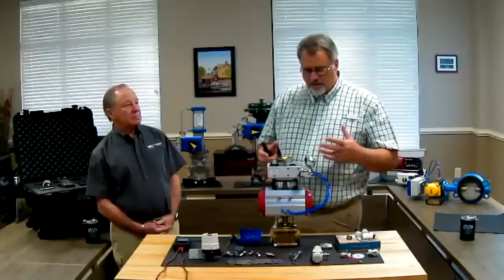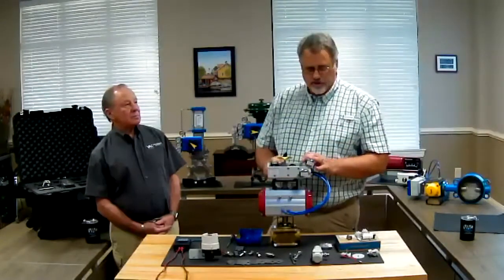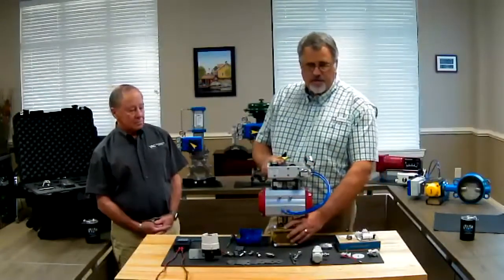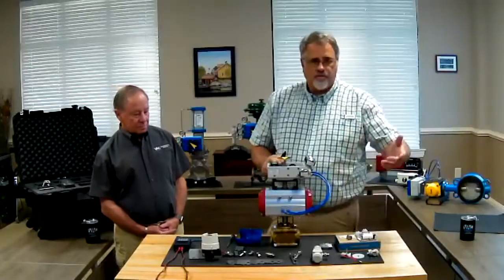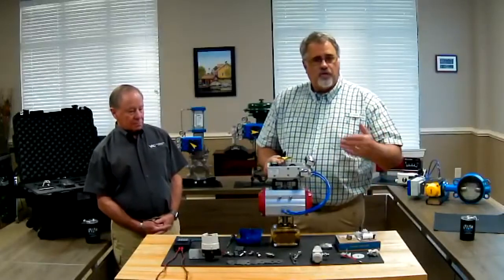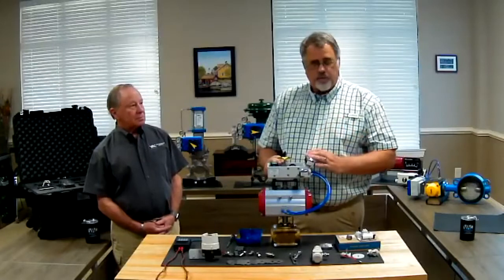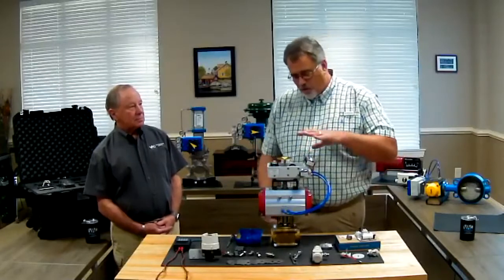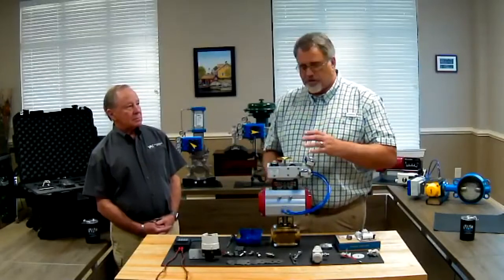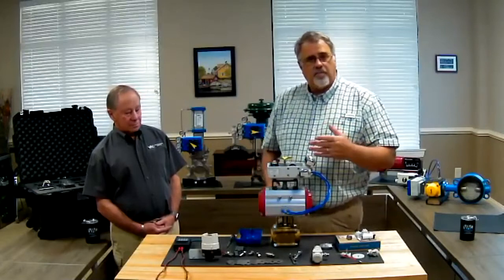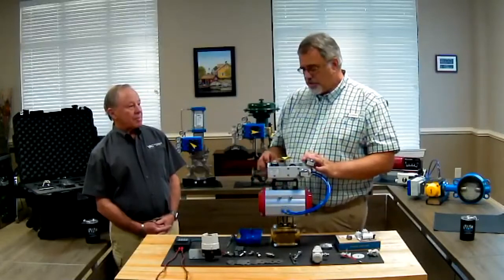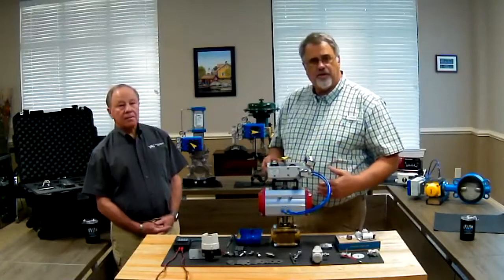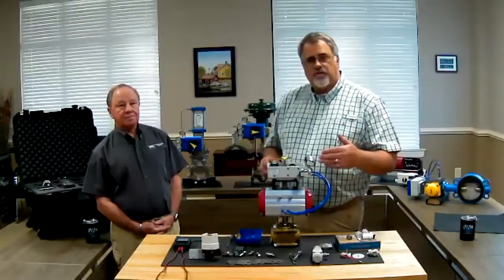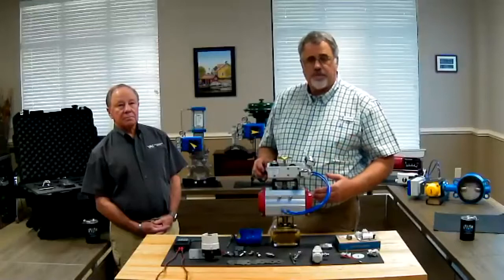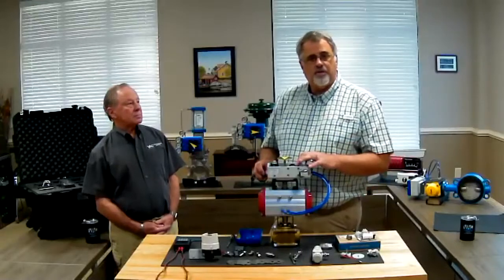Carrying an assembly like this is not all that difficult. And then we've got the valve. In this case, it's a live loaded stem packing. And why is live loading good for a modulating valve? It's always moving. So these are things that you can talk about with the whole package when you're first introducing yourself and talking about the positioner, but you have the opportunity to talk about these other items. And as customers ask you questions, you may wind up selling an actuator while you're demonstrating a positioner.